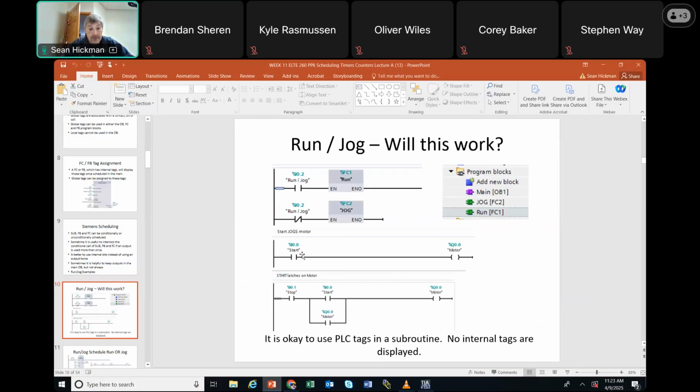And so if I'm running inside of here, I hit the start button, the motor comes on. And that would be if the jog was true and it was called. And if this was true, then this would be false. So therefore, I'd used an output more than once. But it can only be true either in this case, because that's true and this one's false, or in this case, when this is true and that's false. So I used a motor output more than once.